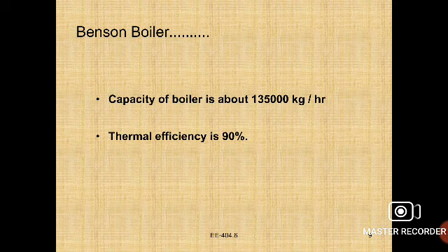The thermal efficiency is 90%. Actually, in the boiler, steam can be produced at about 225 bar pressure, but it requires large energy to operate the pump. So if 225 bar pressure is there, we need large energy to operate the pump. For this reason, it is operated at only 210 bar.